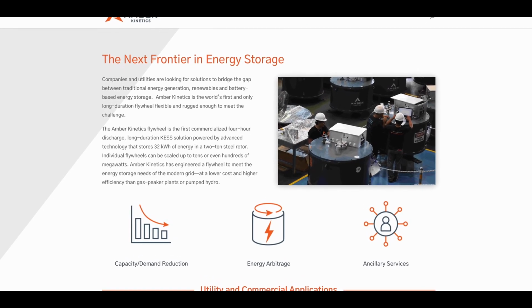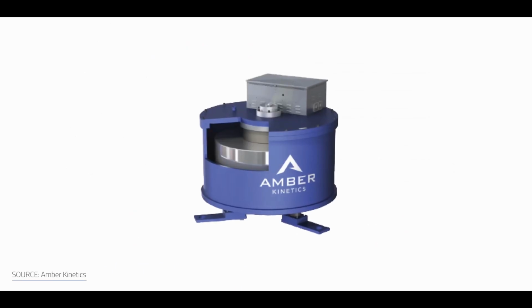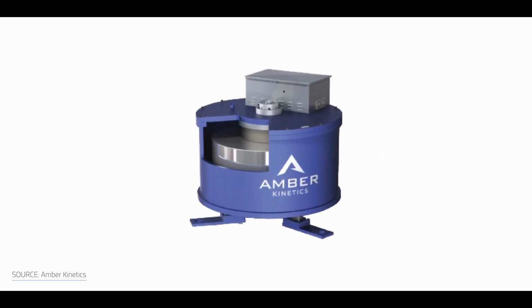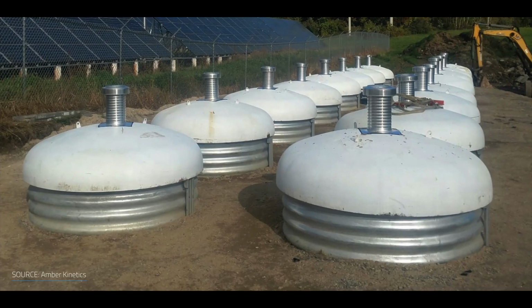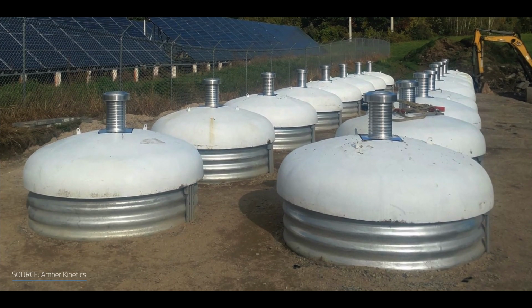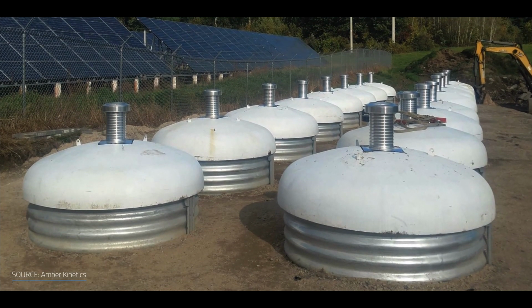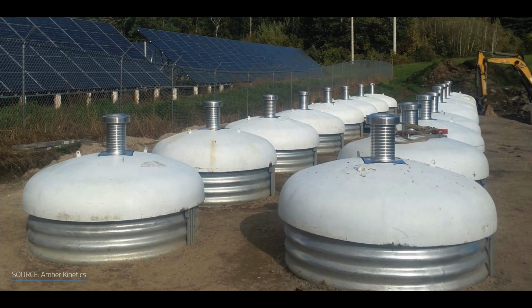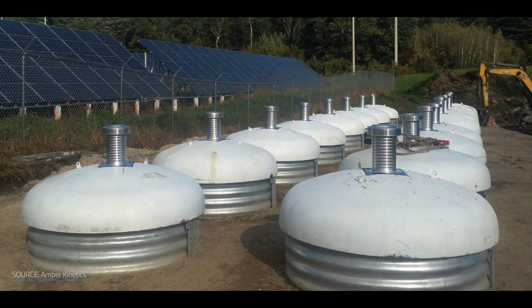Another company playing this game is Amber Kinetics. Their all-steel M32 model can provide 8 kilowatts of power for 4 hours, achieves efficiency higher than 86%, and offers 11,000 cycles. In 2018, the company, in partnership with West Boylston Municipal Lighting Plant, commissioned a 128 kilowatt, 512 kilowatt hour flywheel energy storage system in Massachusetts.